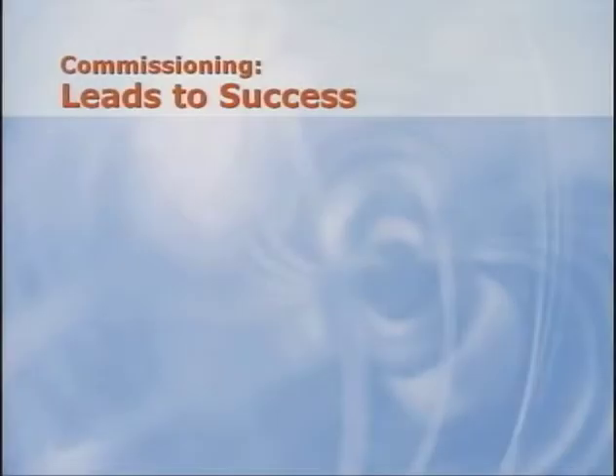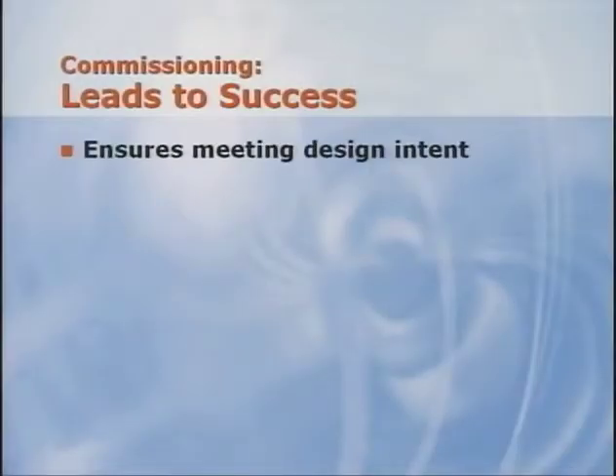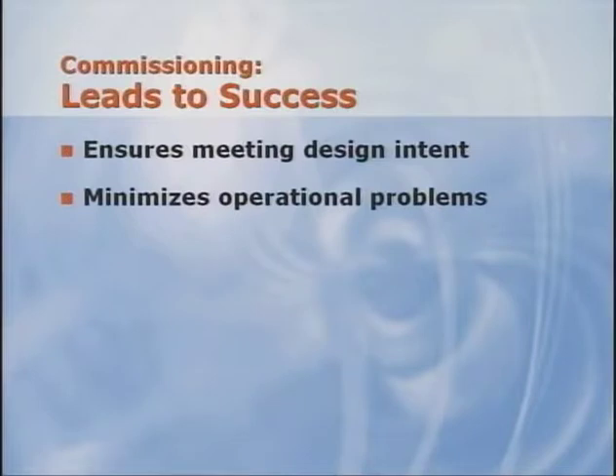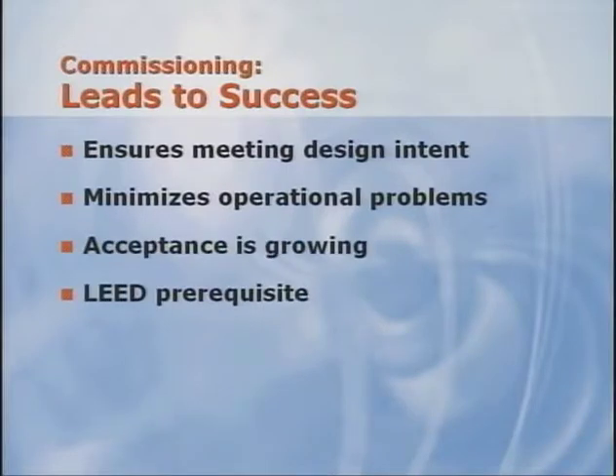That's right, Jeannie. You should consider commissioning for all of your projects. Our experience has shown that most operational issues could have been avoided if the HVAC and control systems were commissioned. Commissioning is the only way to ensure the systems are operating per your design, and studies have shown the additional cost to perform commissioning is far offset by the cost saved to fix problems later and the potential energy savings lost due to poor operation. It's also a prerequisite if your customer is considering LEED certification, and you can also get an extra point for additional commissioning activities.